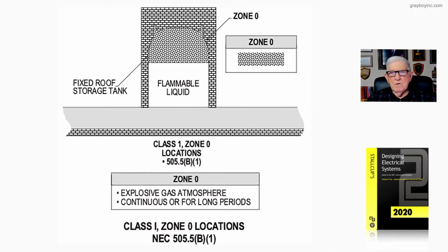Now let's review this figure 21-59, and we're determining a Class 1 Zone 0 location in accordance with NEC 505.5(B)(1).